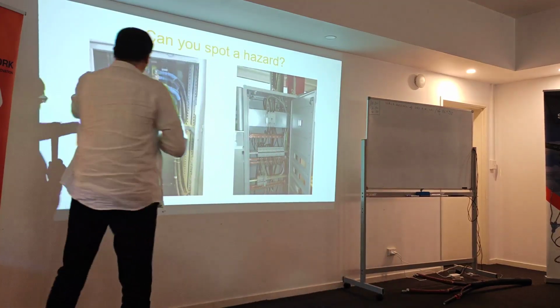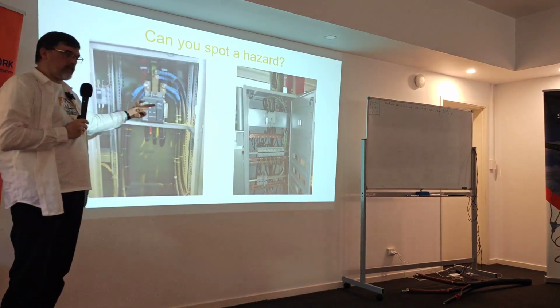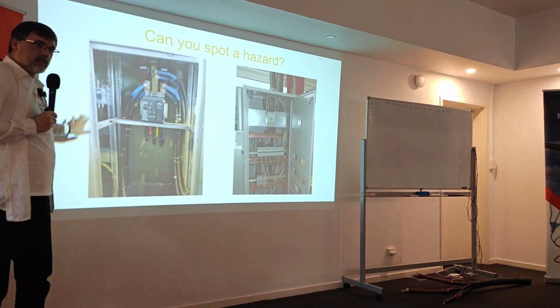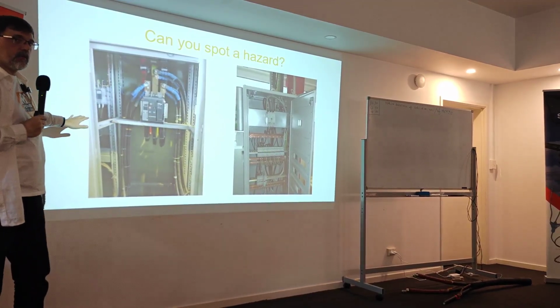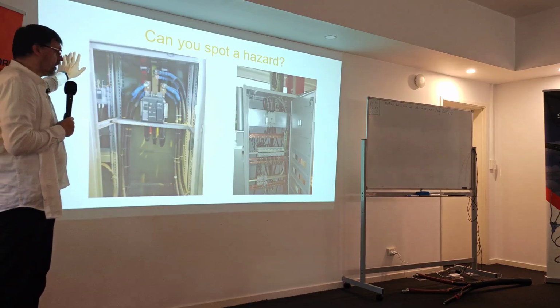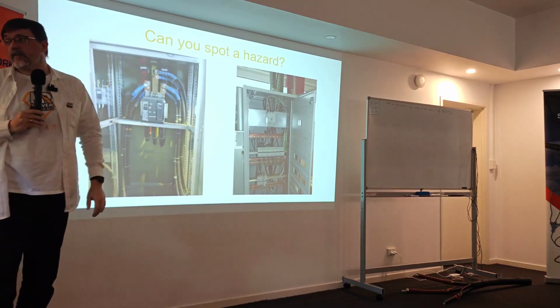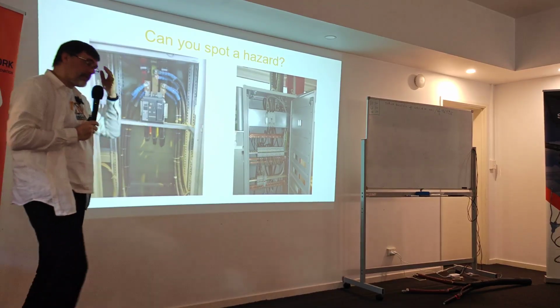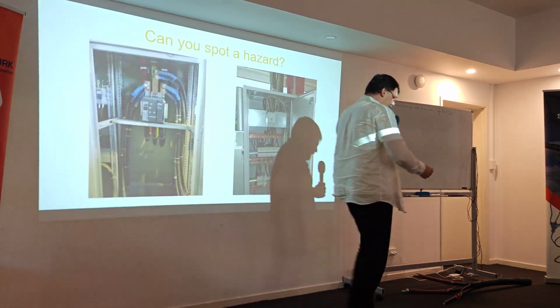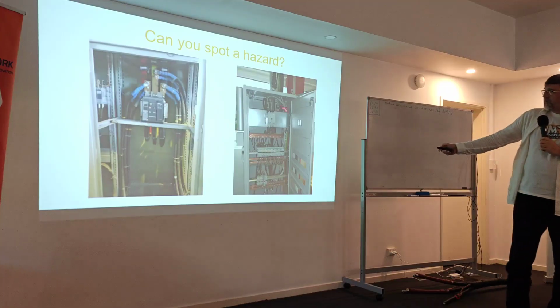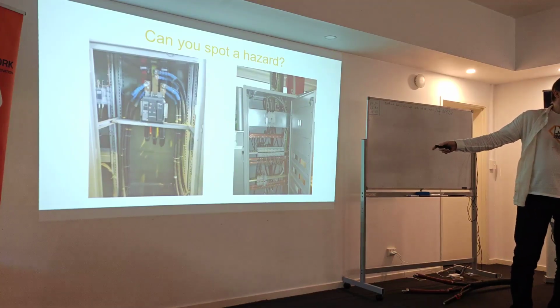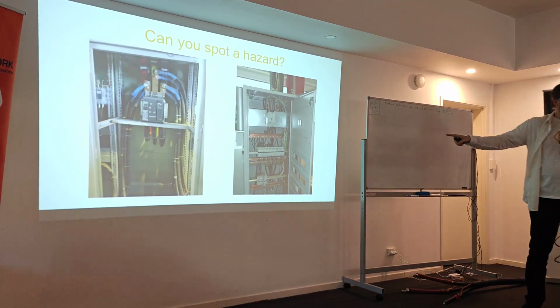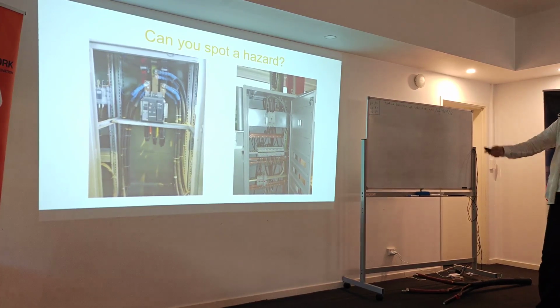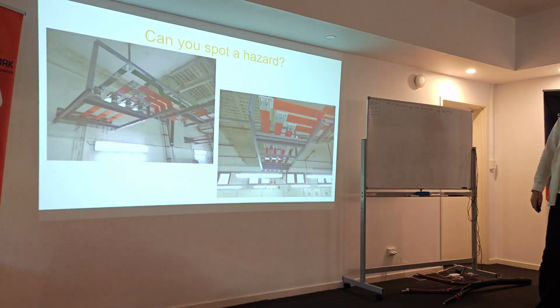Fun thing is that technically you don't have to open this to look from the side. And those are the feeders, 160 amp, 100 amps. So despite that you might think this is a safe one, you look to the right and then you see this thing. Yeah? So that's one thing. The second thing is, my problem was that I have to open the doors to see the settings of the breaker. So that's because of me, they have to open it. But then you see everything else. Do you have something like this somewhere?